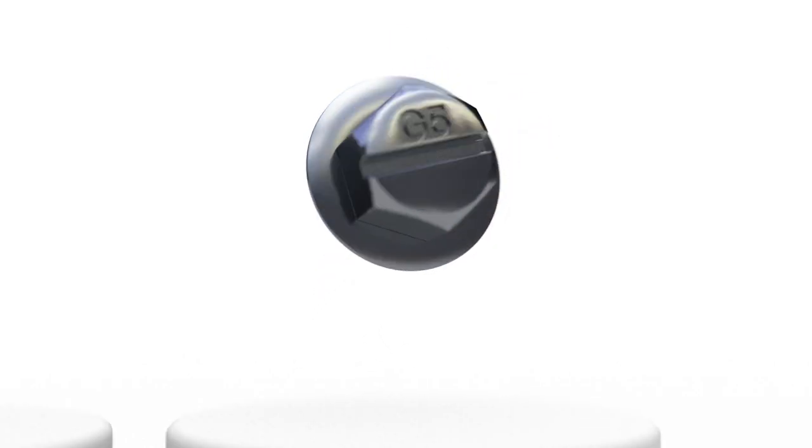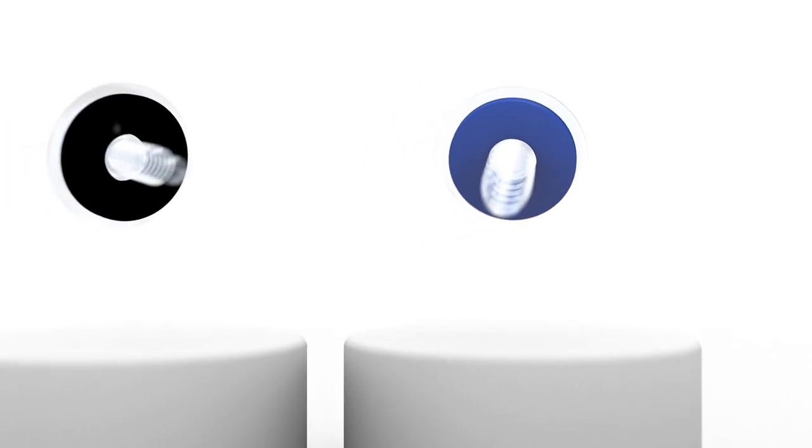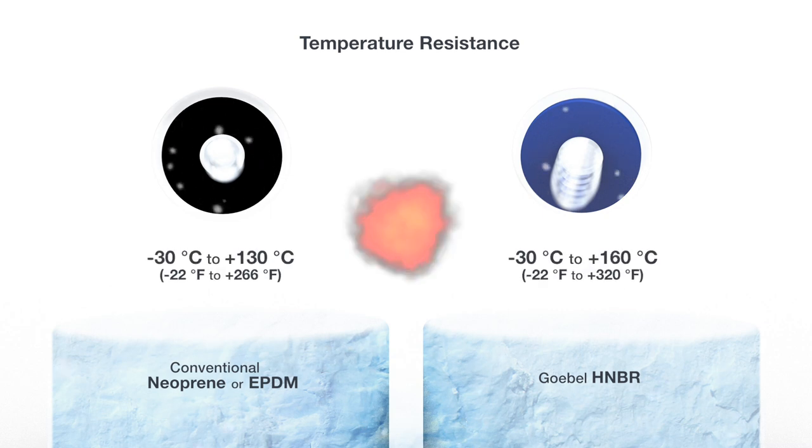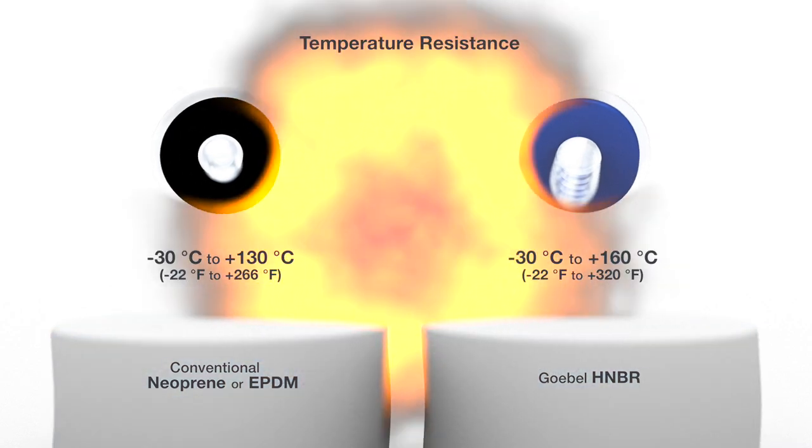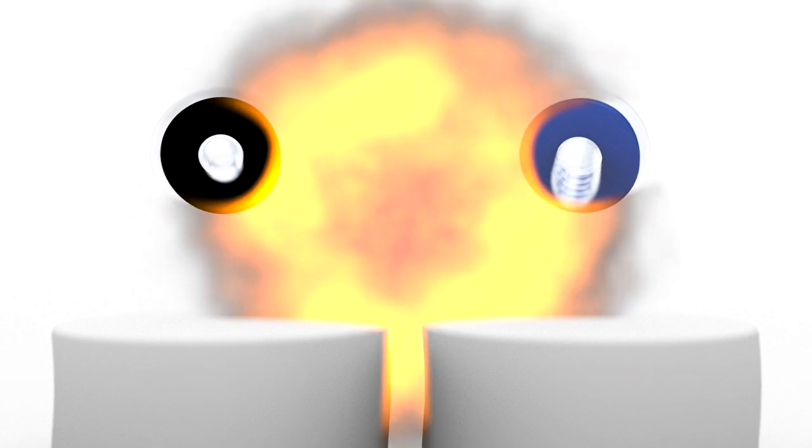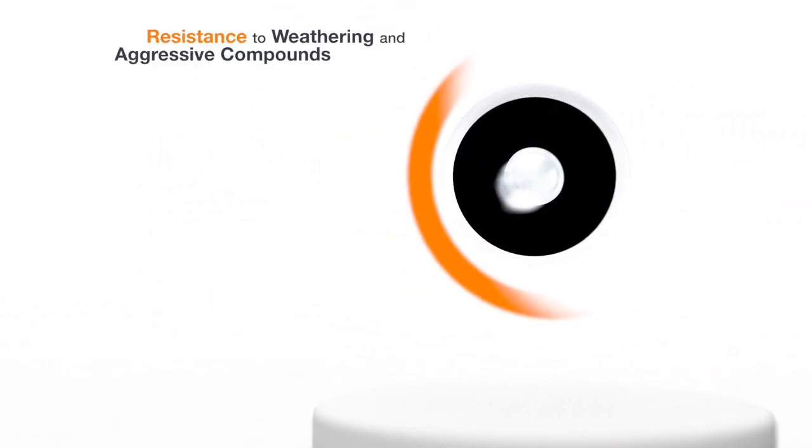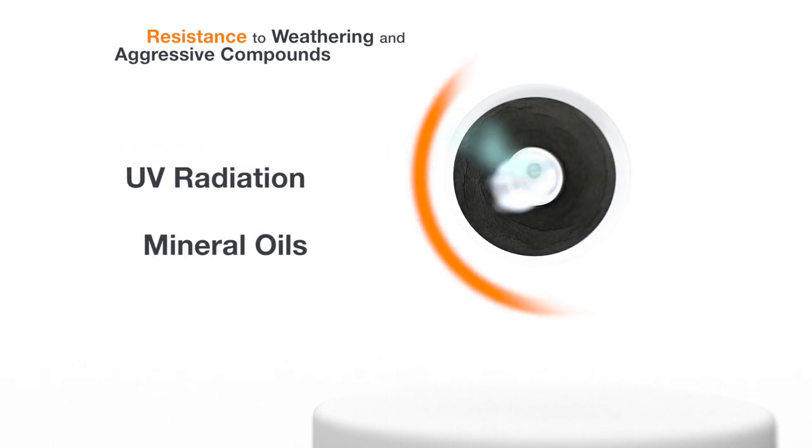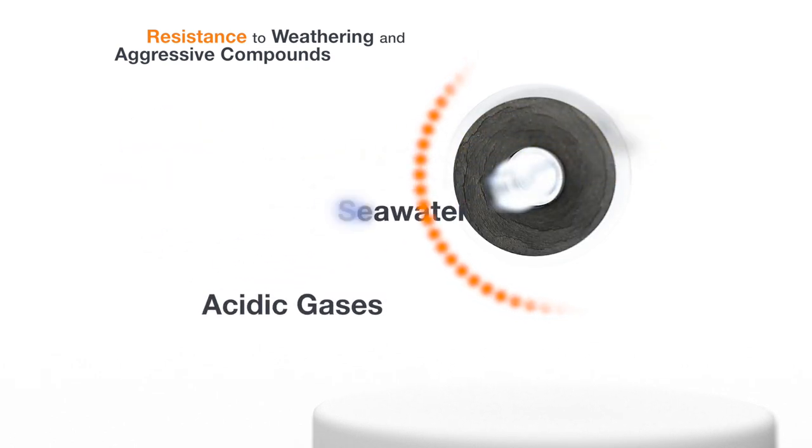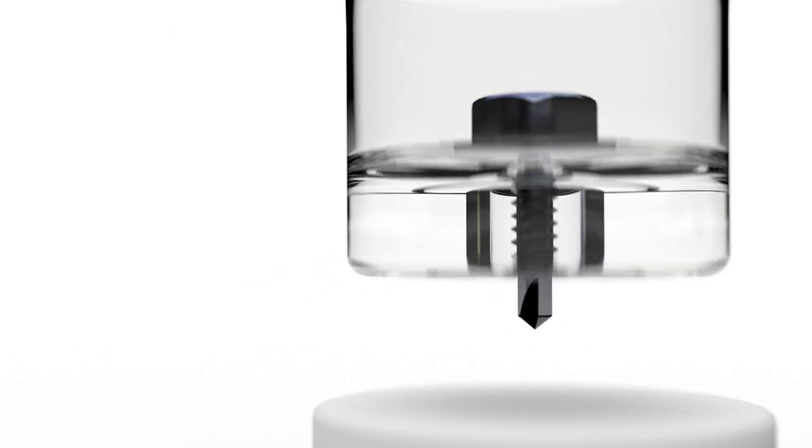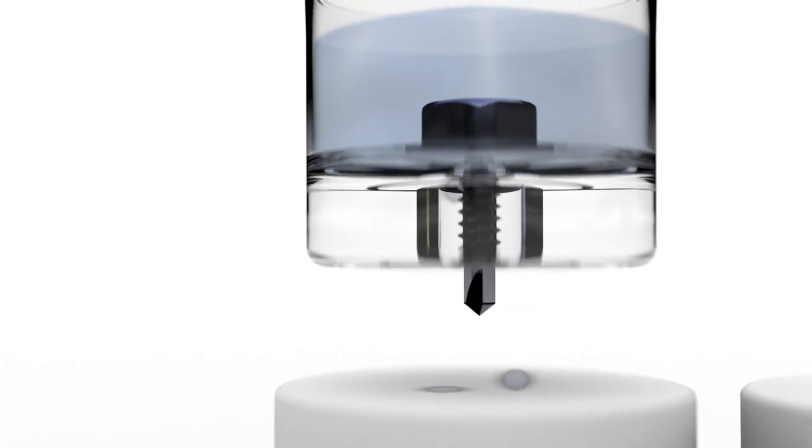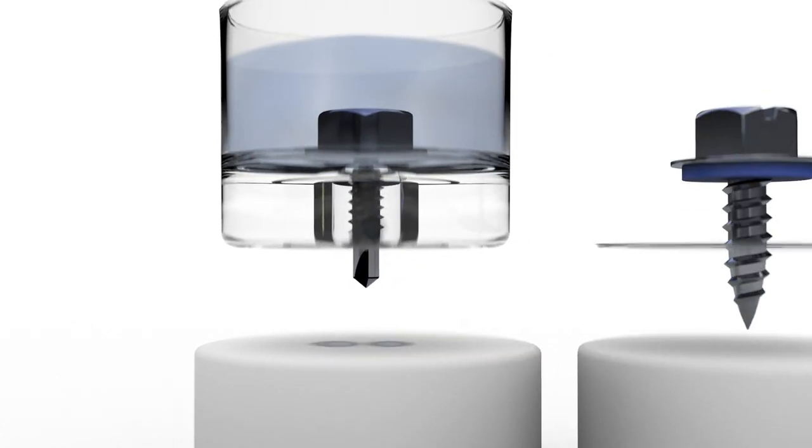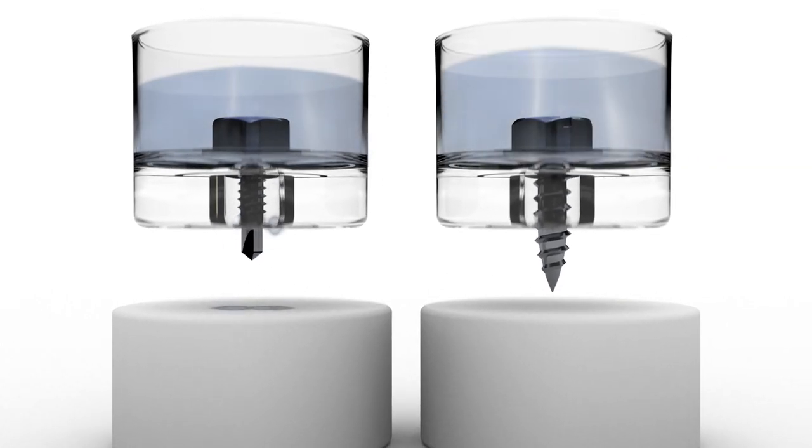The technical difference of the newly developed blue HNBR duplex sealing washer proves itself in a considerably higher temperature resistance, of about minus 30 degrees to plus 160 degrees Celsius. Also in comparison, the higher weathering resistance versus neoprene EPDM, as well as the resistance to mineral oils, ozone, seawater, and acidic gases, prevents early breaking of the sealing washer. This means the penetration of water is almost impossible, and the insulation is not damaged. Therefore, the CUI problem is minimized most effectively.